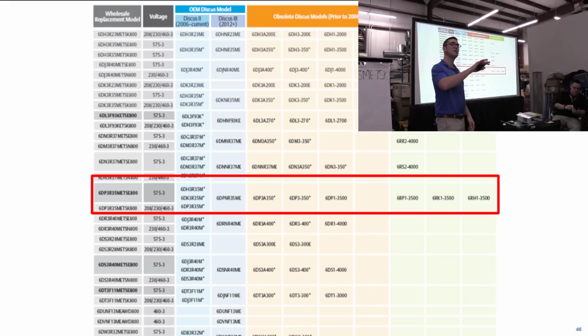Okay, you're out in the field, you check out the compressor and it's a failed compressor. You have open windings. The compressor has to be replaced. Okay? This is the compressor model number right here. You've got a 6RH1 3500. Doesn't really matter what the voltage is right now. So that is what has failed. If we go back, look here, 6RH1 to me is no banks unloading. So it's a standard fixed 6D compressor.